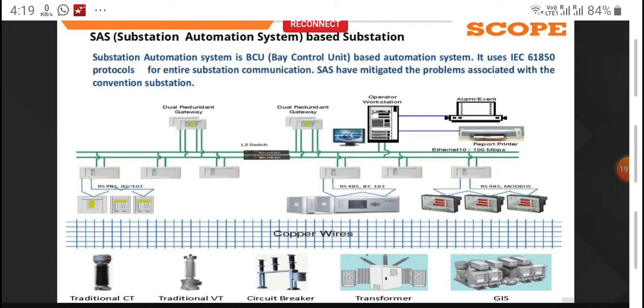But when it comes to the 61850, most of the customers, or most of the electricity boards, have adopted this technology as a standard protocol, and are purchasing their relays with the 61850 feature. So communication from the relay to the substation automation system is mostly happening on 61850. Or some relays still have the Modbus protocol, which communicates to the substation automation system.